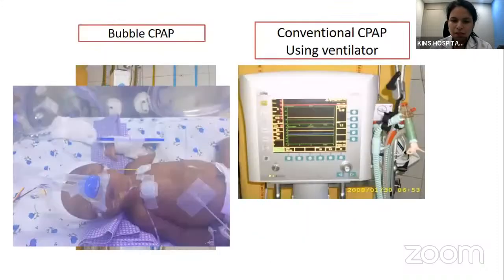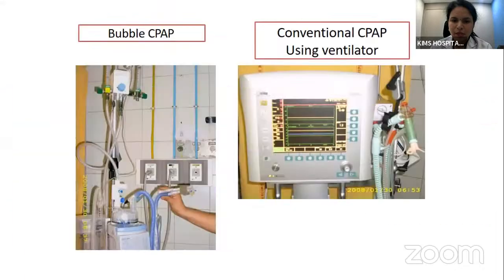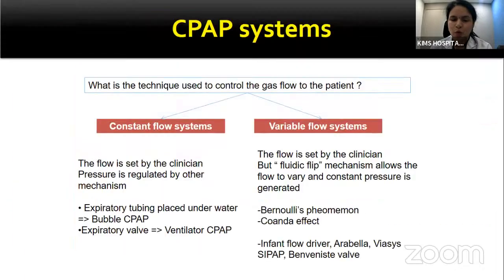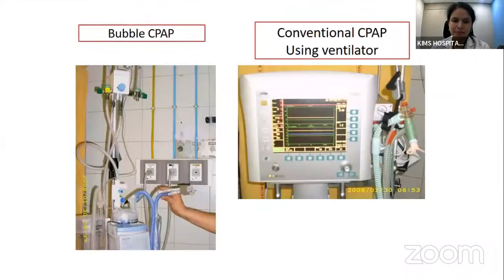So in order to understand the variable flow systems, we would have an open limb wherein additional flow can be entrained during inspiration, which is called the Venturi effect or Bernoulli's phenomenon. And during expiration, some of the gas flow or the bias flow is redirected back into the open limb into the atmosphere, which is called the Coanda effect, and this manages to vary the flow to a higher flow during inspiration and to a lower flow during expiration. And this variation is believed to reduce the infant's work of breathing.